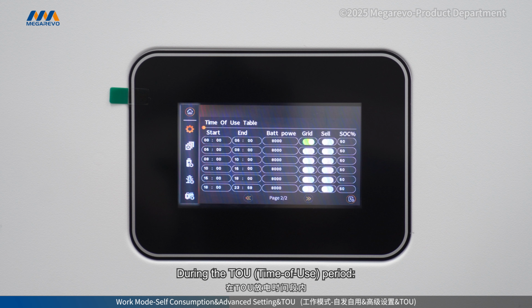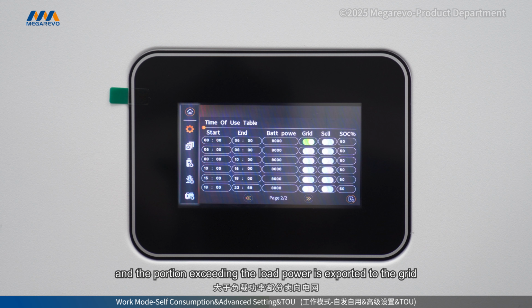During the TOU time of use period, when cell is set to disable, the battery only discharges to supply the load. If the configured BAT power is greater than the load power, the battery discharge power equals the load power. When cell is set to enable, the battery is allowed to sell power to the grid. If the configured BAT power is greater than the load power, the battery discharge power equals the configured BAT power, and the portion exceeding the load power is exported to the grid.